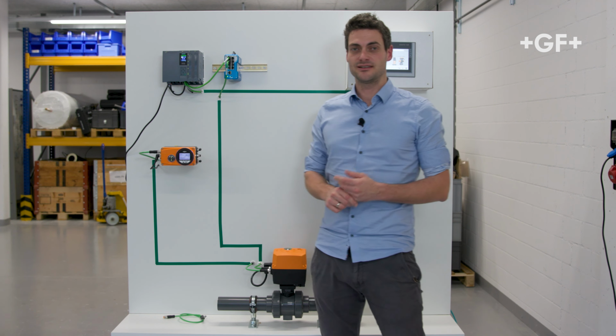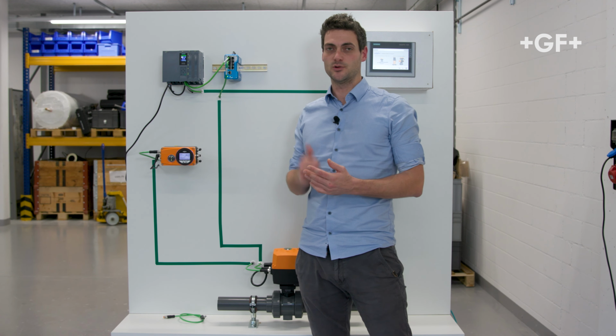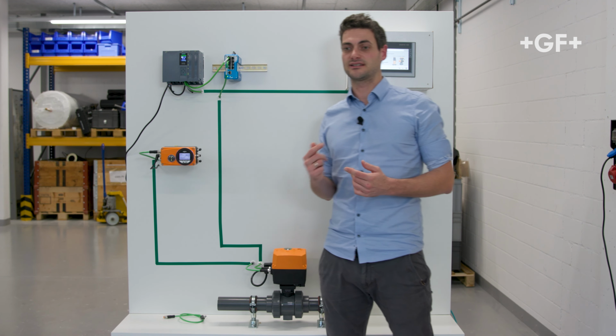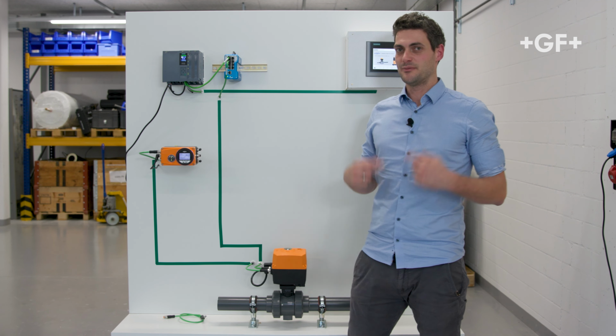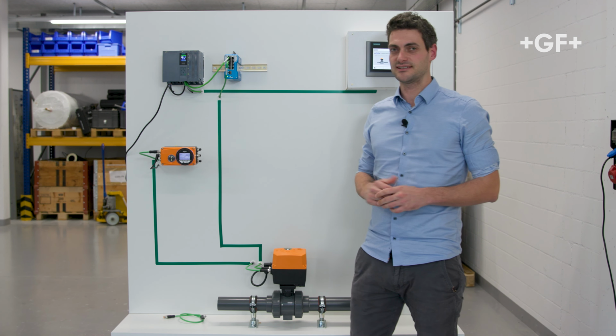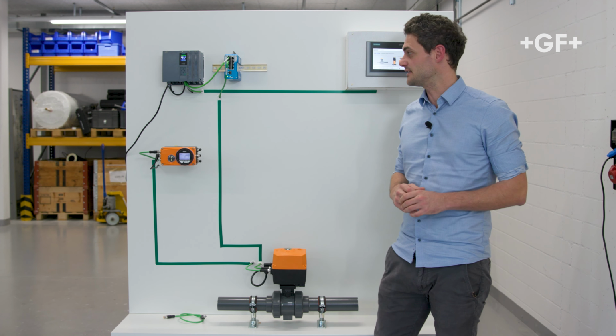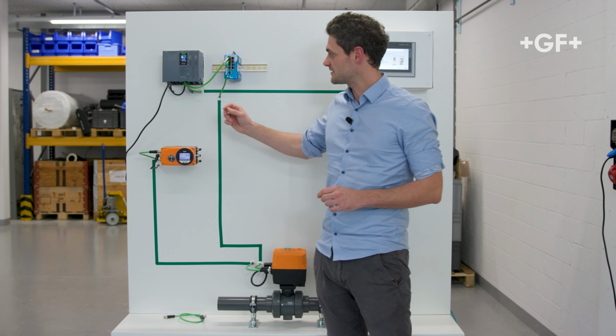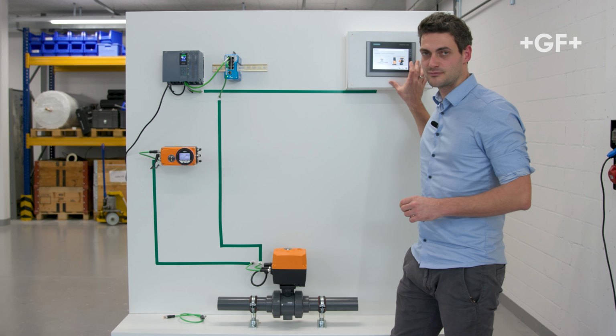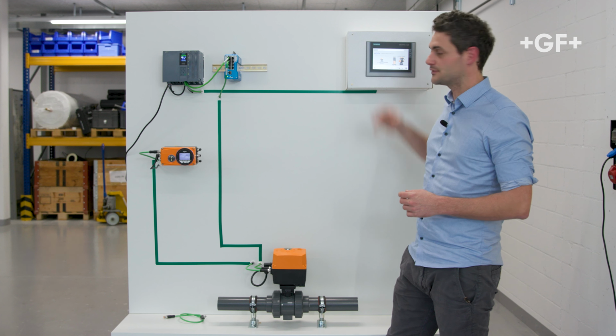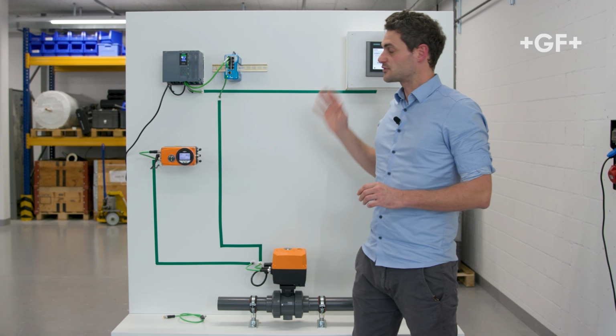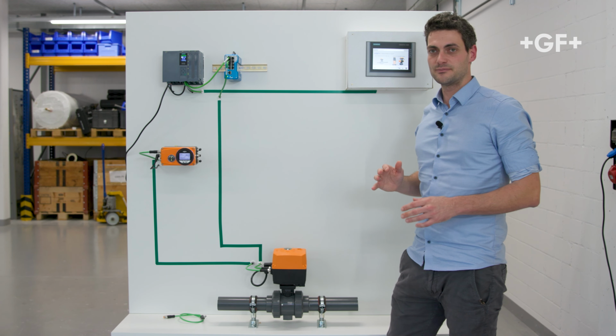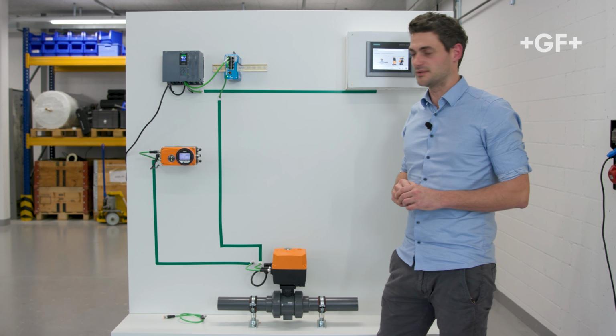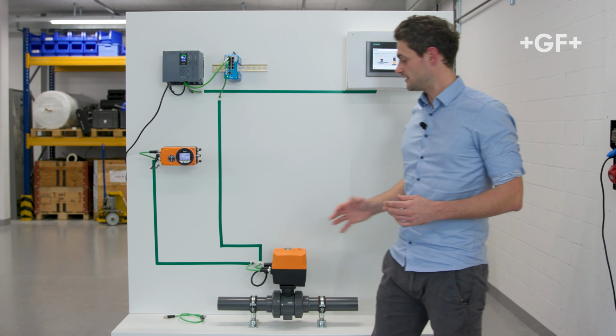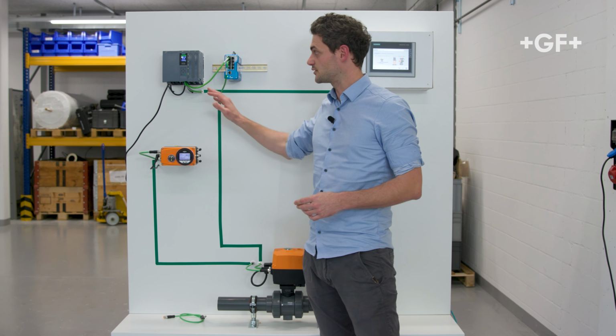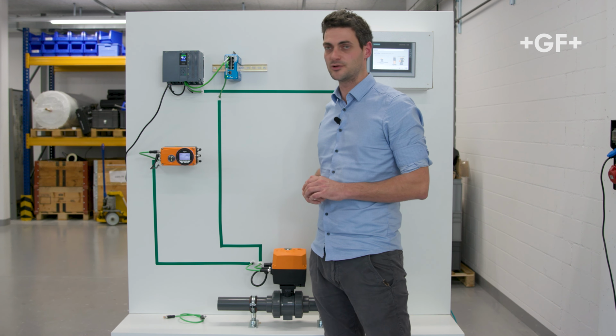So far, we have seen that we can reduce the number of I/O cards. We can reduce the cable effort significantly. But now let's take a look at which additional data is now available with Industrial Ethernet. For this, let's take a look at the HMI. This is just an example, in this case also from the company Siemens. This could also be any kind of SCADA system, or even any kind of cloud environment, because the data itself is transmitted from the device to the PLC, and from there you are open as to how to use it.